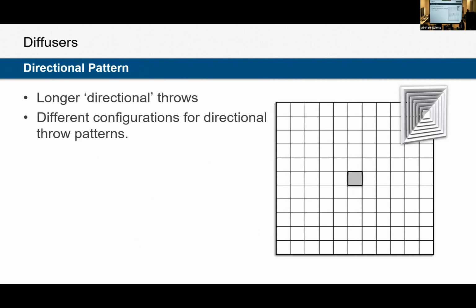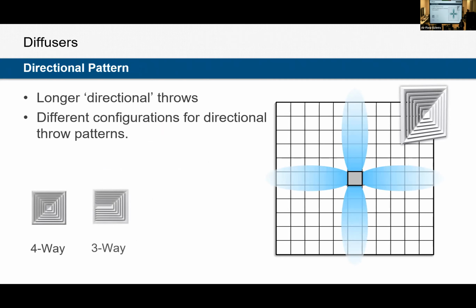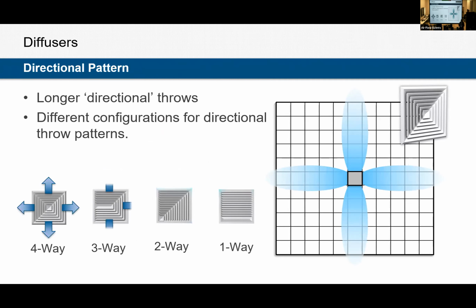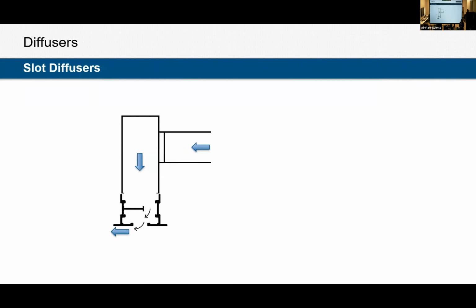The benefit of the directional diffusers is that they have longer throw lengths. So we're not discharging at 360 degrees. We're isolated now to 1, 2, 3, or 4 directions. So we can get longer throw out of a lower number of discharges. So many animations. 1, 2, 3, 4-way. This would be nice if we put it up against a wall. We can get 3-way. This is nice for in a corner if you need to go out 2 directions. 1-way, maybe in the middle of a wall, pointed straight out into the middle of the space. Oh, nice smoke video. There we go.